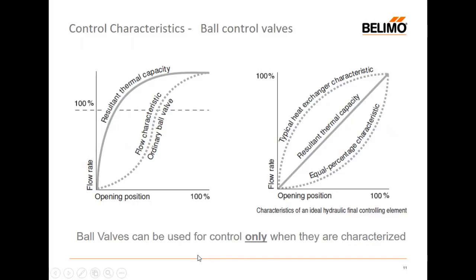If I wanted, I could think about using a ball valve to control. They are increasingly being used for control, but they're not entirely suitable if they're not characterized. If I used a regular ball valve, you can see as I open the valve, it's quite slow, but then it quickly accelerates, and I've got a complete flood of flow here with a tiny movement on this axis. I get a huge increase in flow and then it softens off at the top there. So not really going to give me the nice modulating effect that I need.